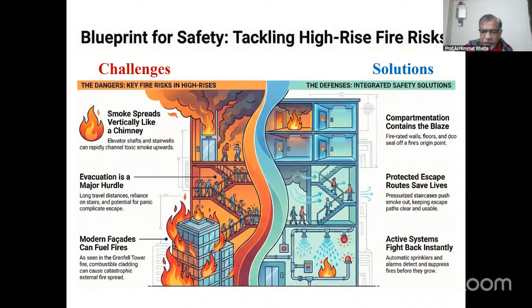Another challenge that we see in the bigger context is limited access, which requires specialized equipment to reach the vulnerable places. Then smoke control. Smoke spreads very fast in the building, so it should also be controlled. All the doors which are made for fire safety should not allow smoke to enter the next room. Compartmentation, which we already saw, is not only protecting the fire from reaching the other room, it is also protecting the smoke from reaching the other room. Otherwise, people will inhale the smoke and die in the panic.